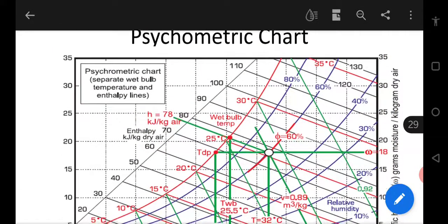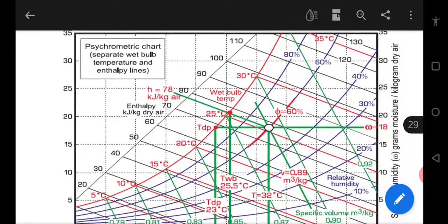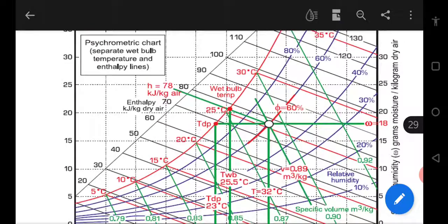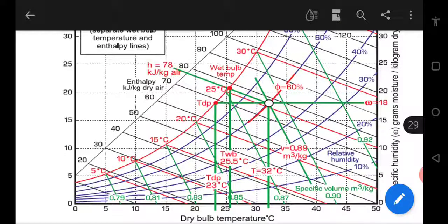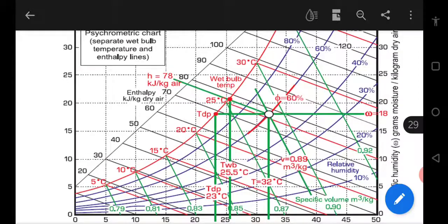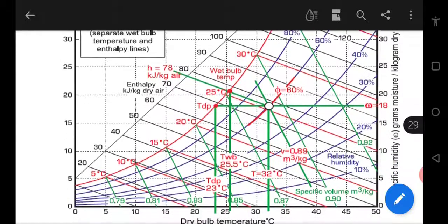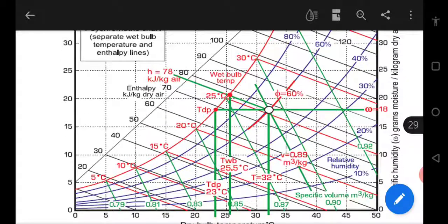Then this psychrometric chart, a very simple multicolor psychrometric chart I could find on the net. The x-axis shows the dry bulb temperature right from 0 to 50 degrees centigrade. This is what we operate in. And then the y-axis 5, 10, 15 to 35 is the grams of water per kg of dry air. That is known as specific humidity.